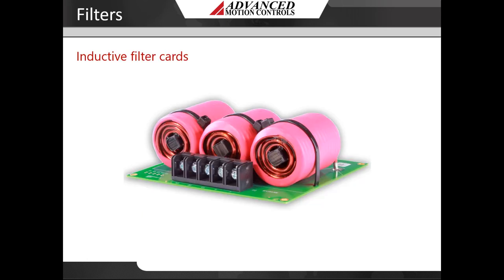Inductive filter cards are added in series with the motor and are used to increase the load inductance in order to meet the minimum requirement of the drive. They also serve to counteract the effects of line capacitance found in long cable runs and in high voltage systems. These filter cards also have the added benefit of reducing the amount of PWM noise that couples onto the signal lines. Higher current spikes on the drive outputs generate higher noise, and with extra inductance added to the system, filter cards help with reducing these current spikes.